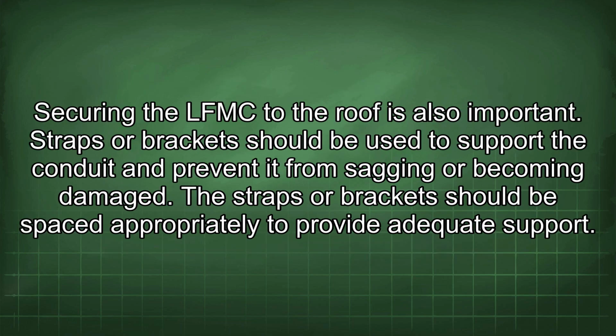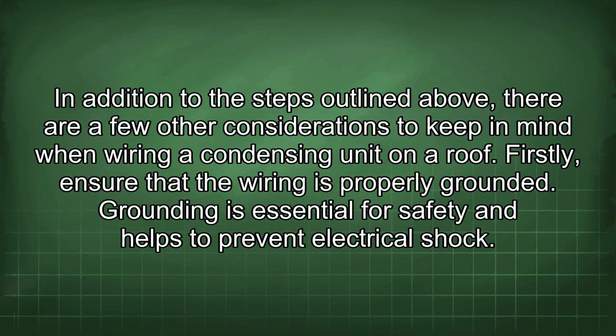Securing the LFMC to the roof is also important. Straps or brackets should be used to support the conduit and prevent it from sagging or becoming damaged. The straps or brackets should be spaced appropriately to provide adequate support. In addition to the steps outlined above, there are a few other considerations to keep in mind when wiring a condensing unit on a roof.